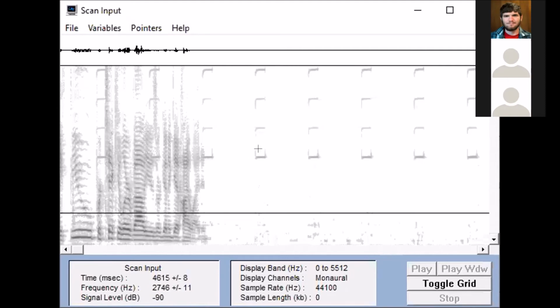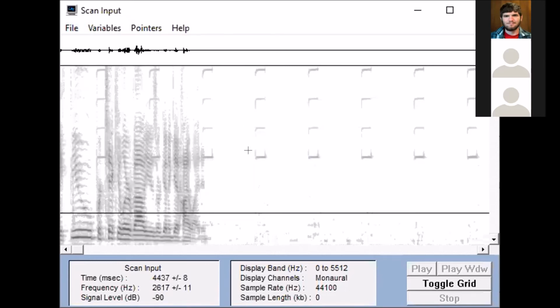Additionally, you'll see on the frequency there's a plus or minus 11. So that is basically how wide each individual pixel on this picture is. So one thing you can do, if I want to get a more accurate value, once I've figured out, okay, I need to be between 2600 and 4000, is go back to the scan input. I can then go to a higher resolution and adjust, a higher resolution, so that's a narrower window.